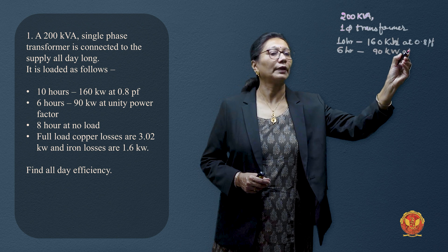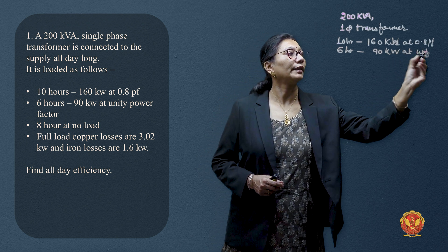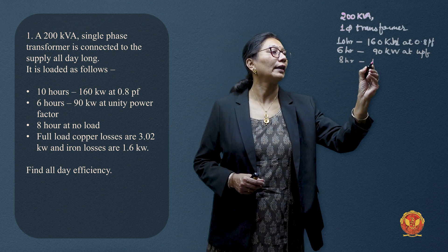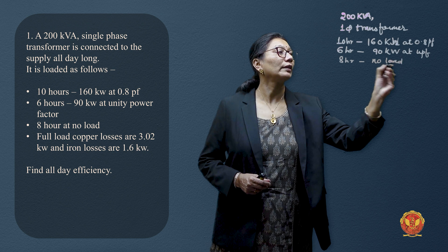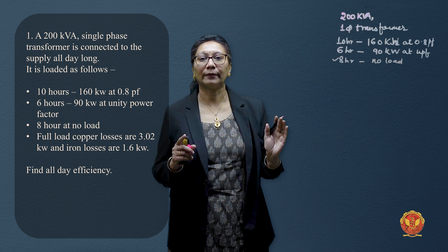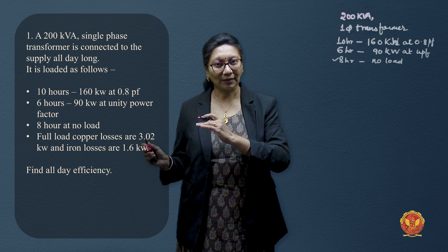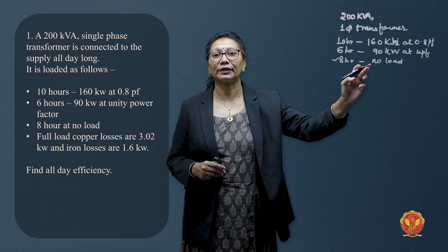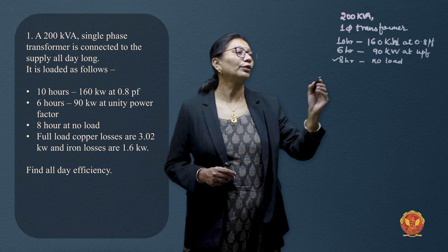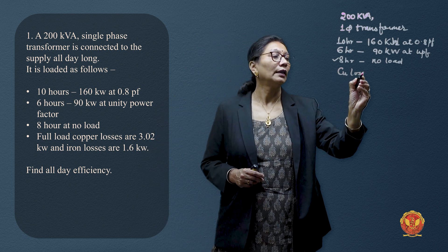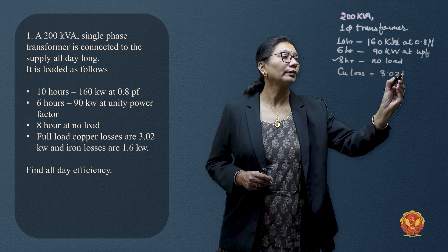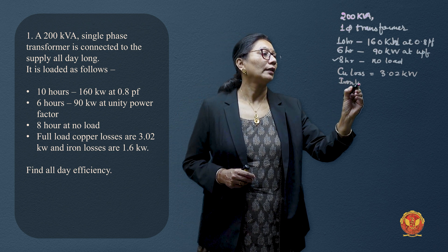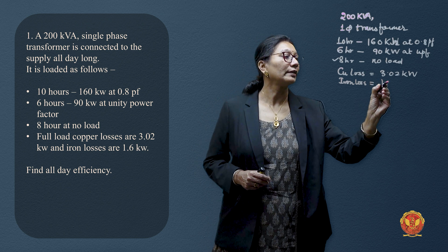For the next 6 hours, power factor is unity (1). For the next 8 hours, there is no load. However, we must account for this period too — even when there is no load on the secondary, primary supply is continuous, excitation is present, and flux is set, so iron losses must be calculated for these times as well. Full-load copper losses are 3.02 kW and iron losses are 1.6 kW.